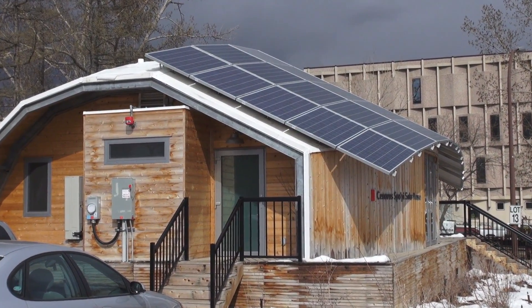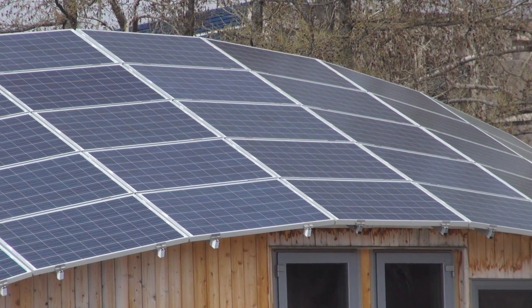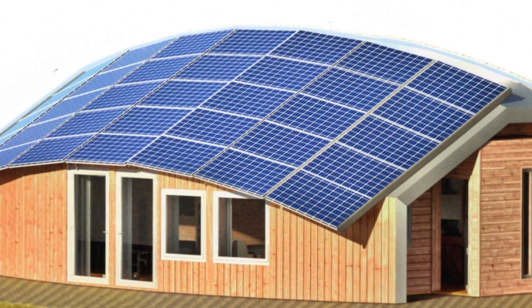One of the challenges they ended up having to solve was optimizing the solar array with its curved turtle shell-like roof. It was a significant engineering challenge, basically looking at how far we could push the boundary of where those panels could be angled from the optimal south-facing exposure. What we found was that with the curvature we finally arrived on, the overall array — which includes 35 panels on the angle and then two on the top, basically flat — is less than 5% less output than you would see having those 37 panels all faced exactly due south at optimal angle over the course of an entire year.